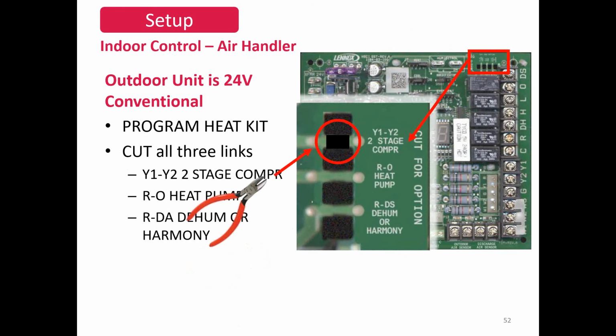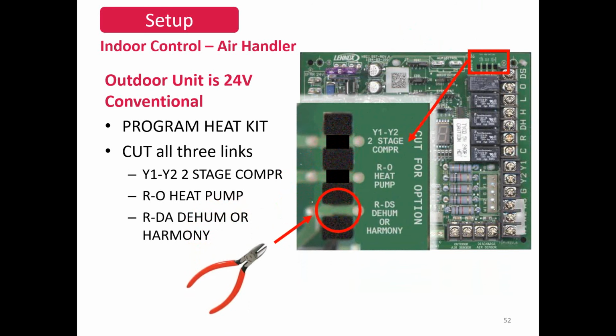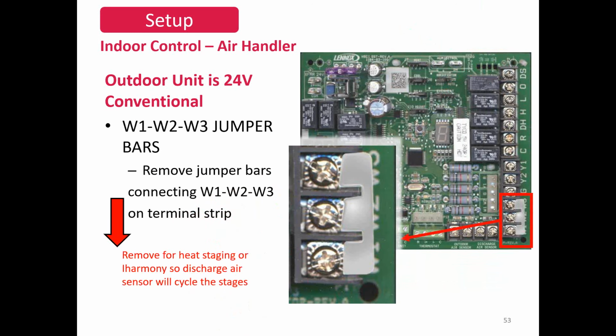The air handler is the very same way. Again, we talked about it a little bit yesterday, but I just want to bring it back up. The air handler does have jumpers on it as well. You want to remove this if you're using iHarmony. This is our jumper for W1, W2, and W3. You can individually trigger those heaters to bring on just a little bit as needed, or you can bring them all on at one time. It's entirely up to you. Maybe you just got a 10 kW heater and you want to trigger it all at once. But if you use the iHarmony or zone control, we have that DAT sensor I talked about where it'll actually control the heater and bring on only what's needed.